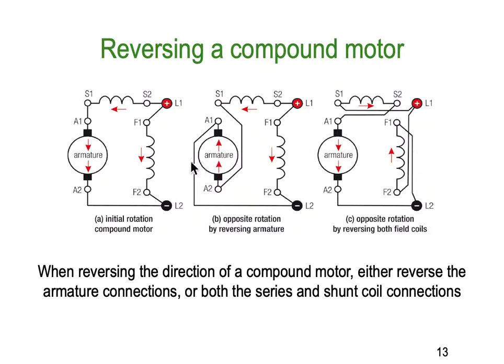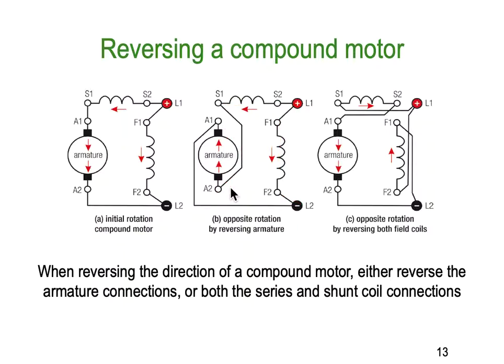Reversing a compound motor: the same applies — you've got to reverse either all the field or all the armature. When reversing direction of a compound motor, either reverse the armature connections or both the series and shunt coil connections. In arrangement A is the original. In B, everything has stayed the same except we've simply reversed the armature connections end to end. In C, the armature has stayed the same direction, but we have reversed that field connection and this field connection — you must reverse both parts of the field in a compound motor.